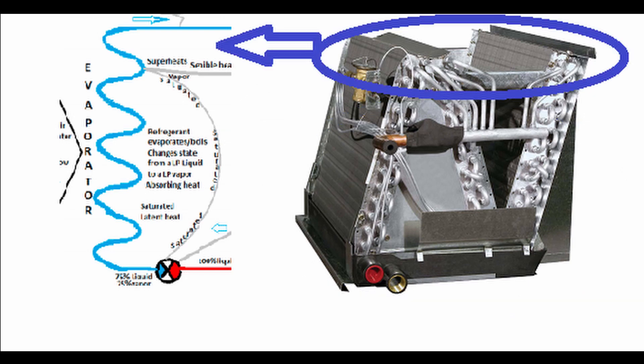After we boil all that liquid into a vapor, we can continue to add heat to it. This is going to be sensible heat — the refrigerant is still absorbing heat but it's now measurable. This is the very last small section of that evaporator coil. This is where superheat starts: the refrigerant is absorbing heat above its saturation temperature, becoming a superheated vapor.